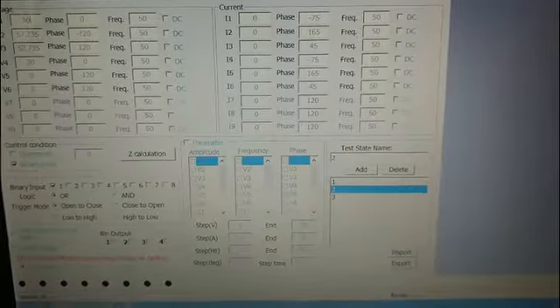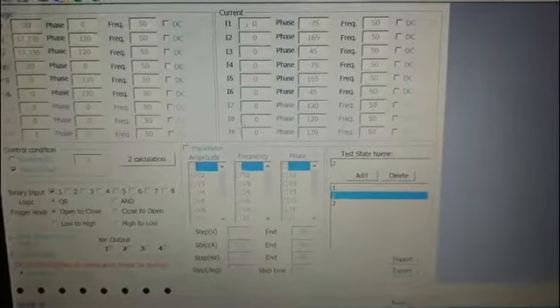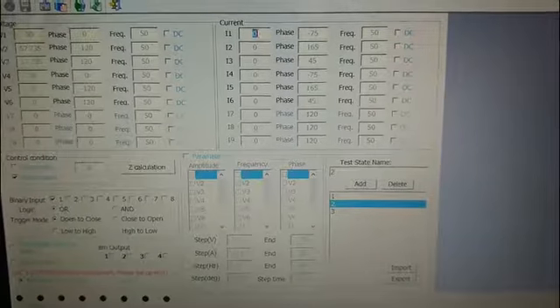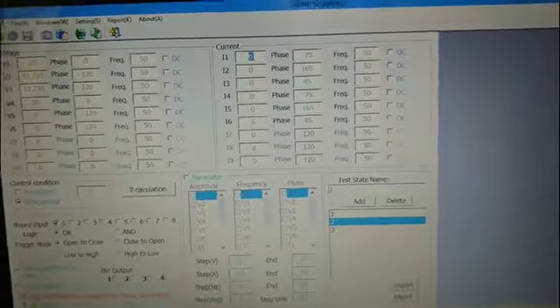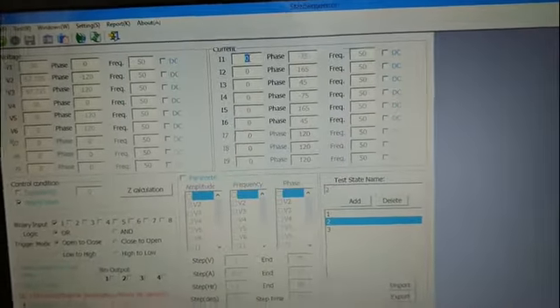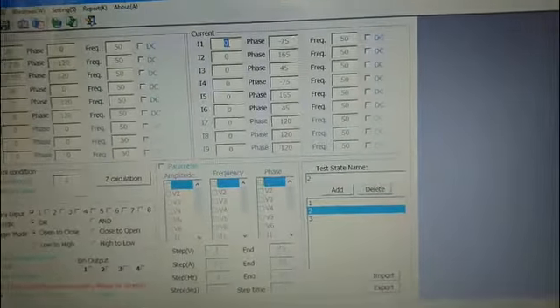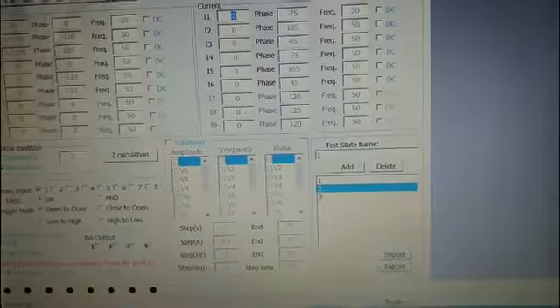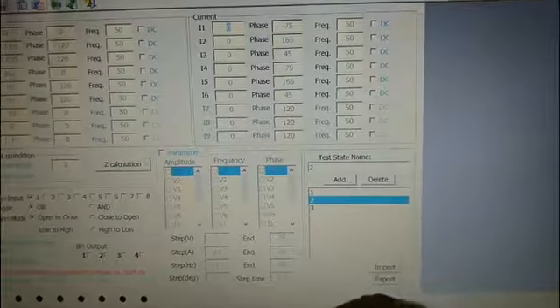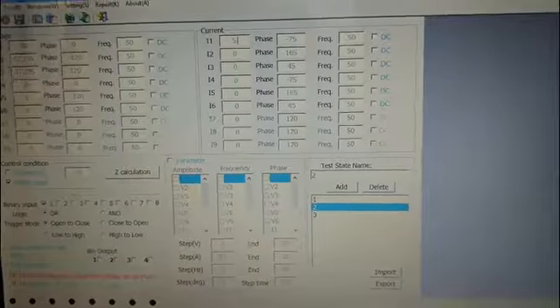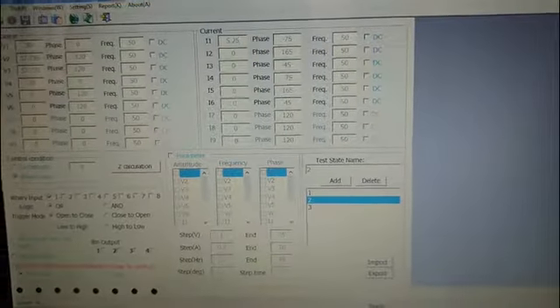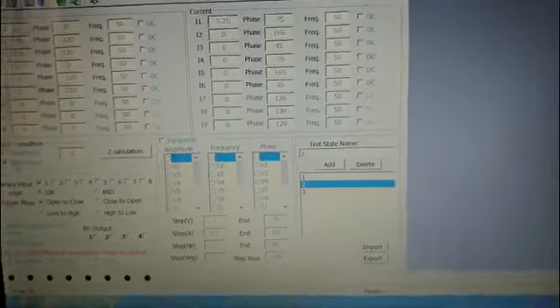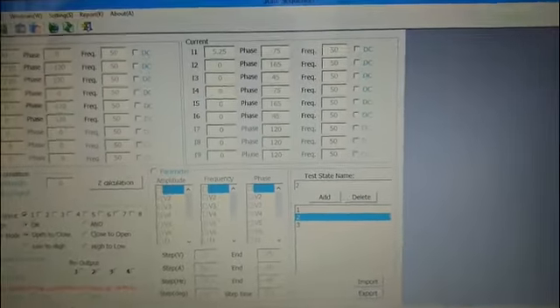We use the first overcurrent relay to do this test. The setting current is 5A, so we input 5.25A and connect the first binary.